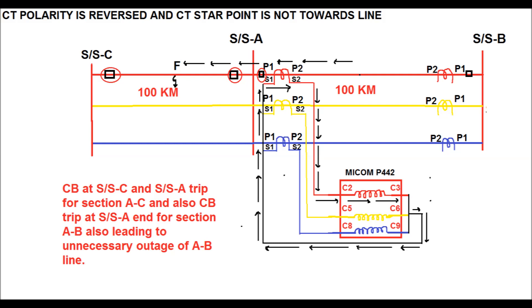That is why the CT polarity should be properly connected on both the primary and secondary sides of the relay, and the CT star point should always point towards the protected object — in the case of a transmission line, the star point shall be towards the line. This demonstrates the importance of CT polarity and CT star point for transmission line protection. If you like my videos, please subscribe to my channel, press the bell button for notifications of future uploads, and do comment with your feedback, which is necessary for the improvement of future videos. Thank you.